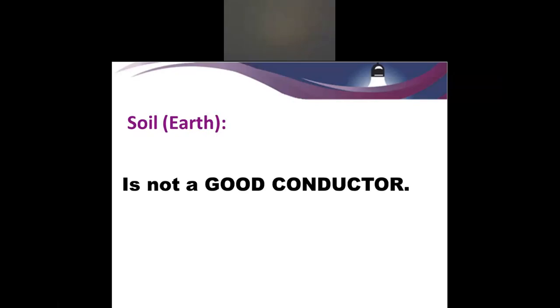Like that, it happens in our electrical system. Whenever neutral is not connected to earth as 0 volts, connecting neutral to earth means we are making neutral as a 0 volt potential. Then only, by that reference point, whatever we measure will be accurate. If that neutral point is fluctuating, floating, then whatever we measure will not hold good, and our equipment is not prepared for more than 230 volts basically.